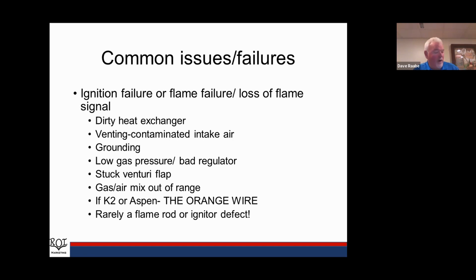It could be a stuck Venturi flap, and I'll show you what I mean by that. I actually have one here, and you can flip your view now if you'd like. But the venturi that we use to pull the air in, see if you can see this. If you notice, there's two ports there. And I'm showing them both open now. The orientation this sits in the boiler is like this. So the bottom flap, the bottom half is closed. And we've run into a couple boilers now that were installed without intake air. So it was a venting issue. Enough grease and grime got in where it held this flapper down or held it up. And that was the cause that we couldn't get the boiler to light, couldn't get it to run properly.